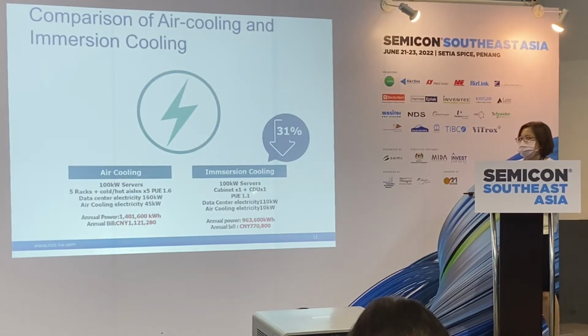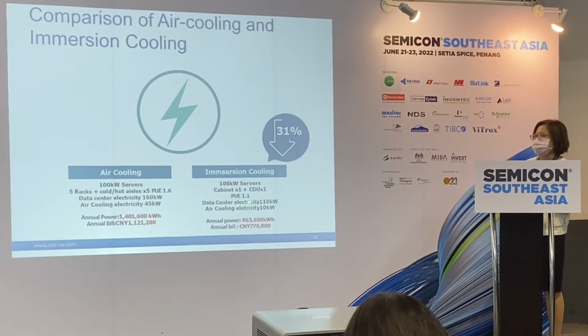The same servers, we only require one cabinet, one CDU, but we can achieve a PUE of 1.1. In this way, you can see the data center electricity will be only 110 kilowatts. For the cooling electricity, it will be 10 kilowatts. So 31% will be decreased. There will be a very huge decrease in electricity, saving a lot on the electricity bill.